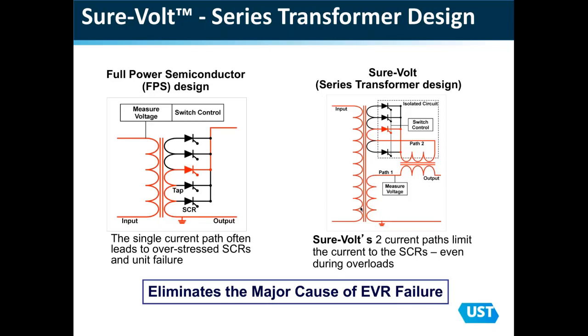The way we do that is, on the right-hand side of the screen is the UST design, and on the left-hand side of the screen is a typical electronic tap changing design by other manufacturers. And you can see we employ a series transformer to protect our SCRs against any faults across the output. Whereas on the left-hand side of the screen, if you have a fault across the output, the SCRs are in direct line with potential failure. Therefore, we do this to give our unit a little more robust capability. And because our SCRs are protected, the weak link in our design is really the magnetics, and the chances of the magnetics failing is quite minimal.